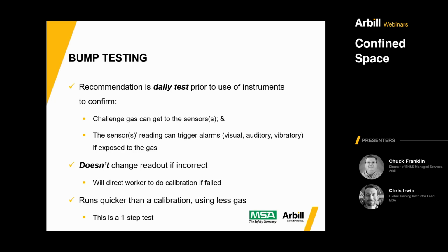So it's not doing everything that the calibration did. If I were to demonstrate this manually, the bump test maybe lasts 15 seconds, whereas the calibration can last 1.5 to 2 minutes. So you can definitely tell the difference. But this is definitely important too. So in my world, we would do bump testing each and every time we use the detector at the beginning of the day, and then we would do a calibration monthly, because that's what I would recommend.